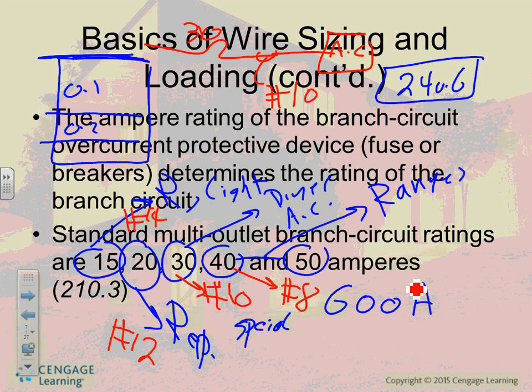You're going to look at me and say, okay, Chad, is this single phase? Yeah. Is it 120? They don't make 120 ACs standing alone with 30 amp. Typically they're 240. They run at 2 hots. So this guy, I have to tell you, is a 240 volt, meaning it's running at 2 hots, no neutral. So how many conductors do I need if there are 2 hots, no neutral? 2. Well, you don't count the ground. So two conductors. So this will be 2 conductors, number 10, gentlemen.